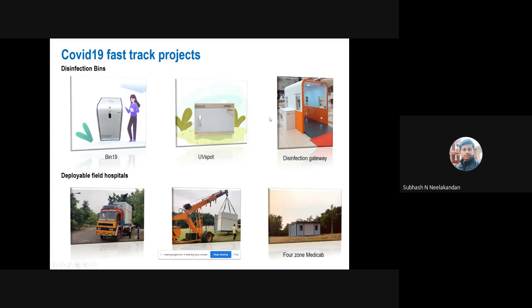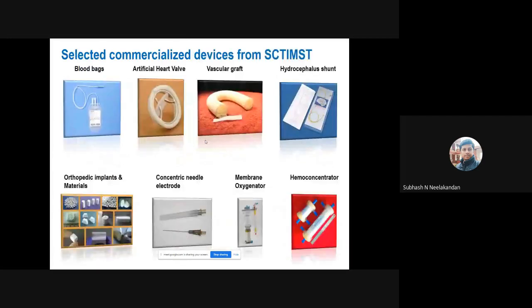So if we go to the device UVspot, this is a low-risk device which will require the least number of tests when compared to an artificial heart valve, which will require close to 7 to 10 years of testing prior to clinical trial. So this is to give a brief idea about the testing requirements for different products.